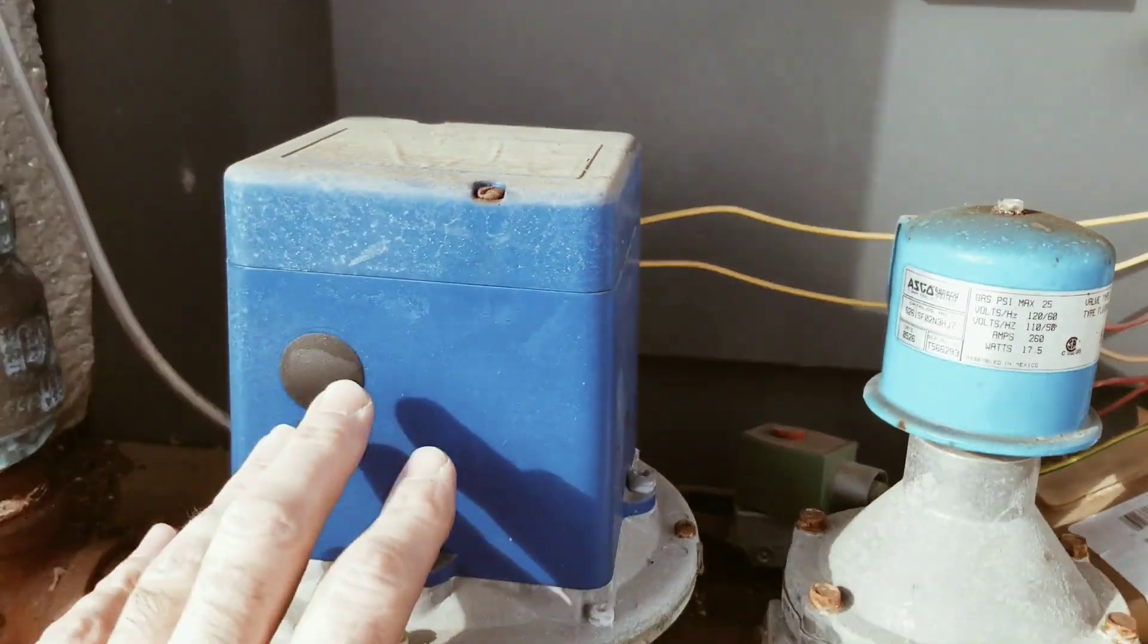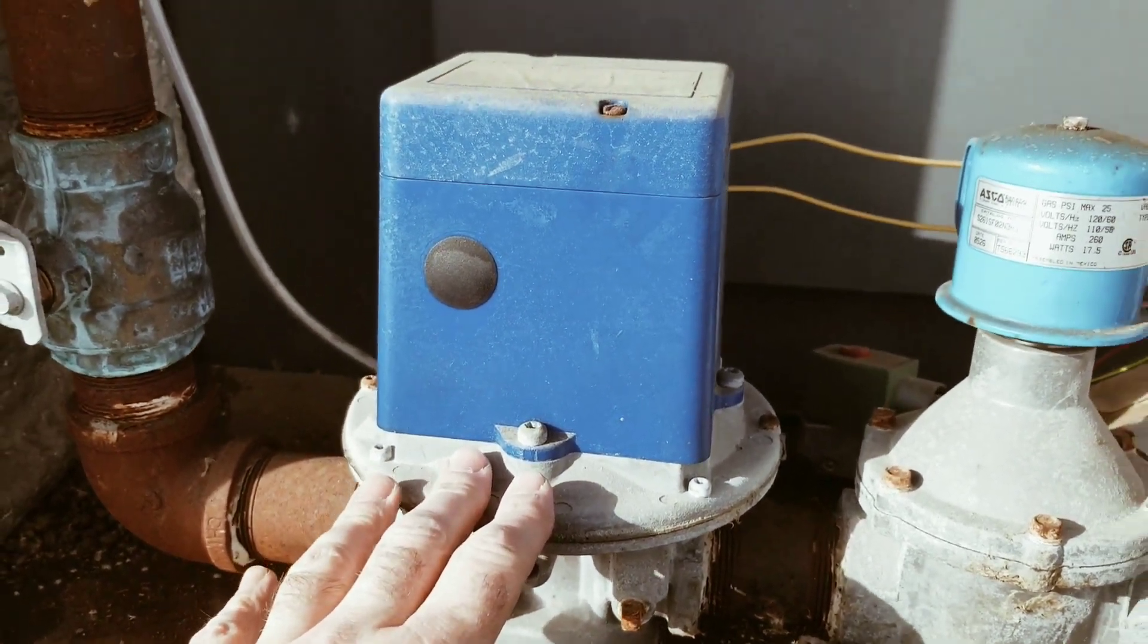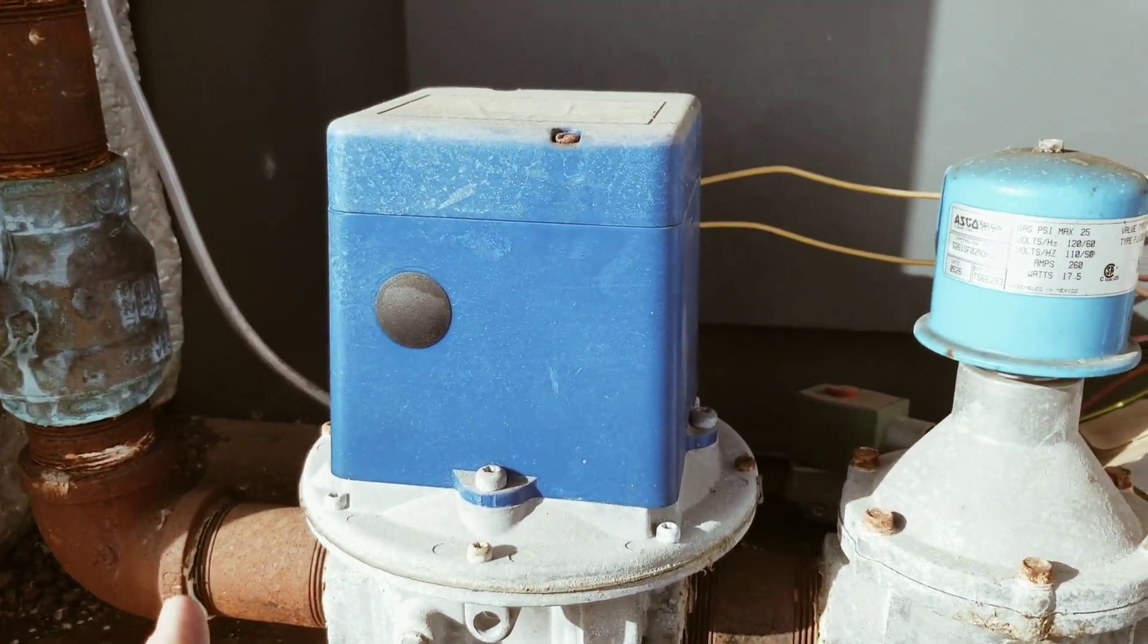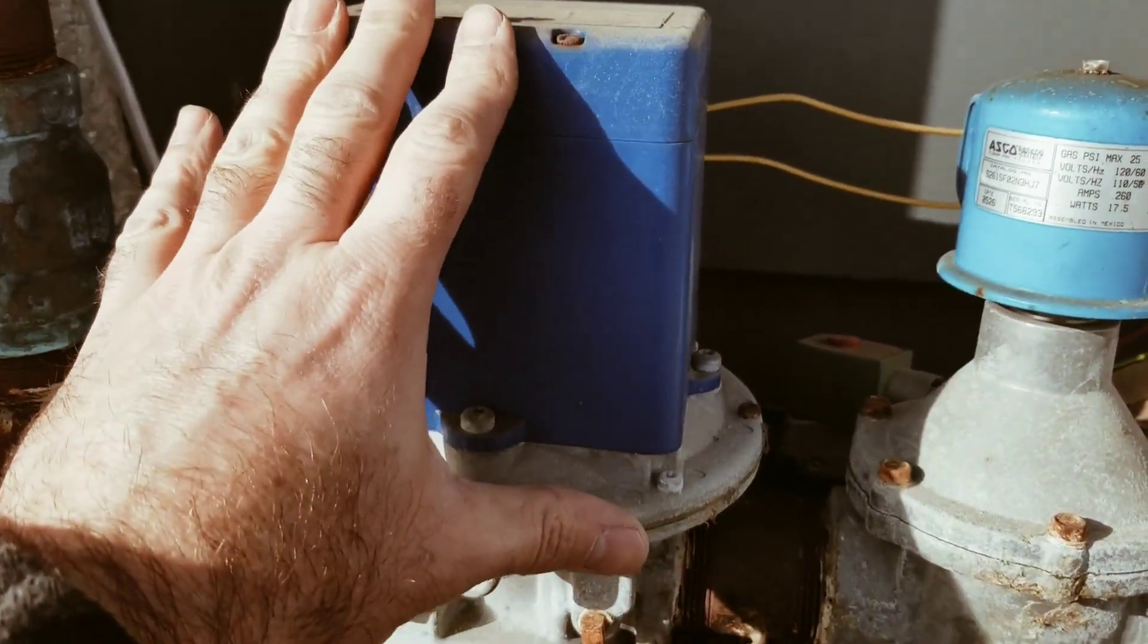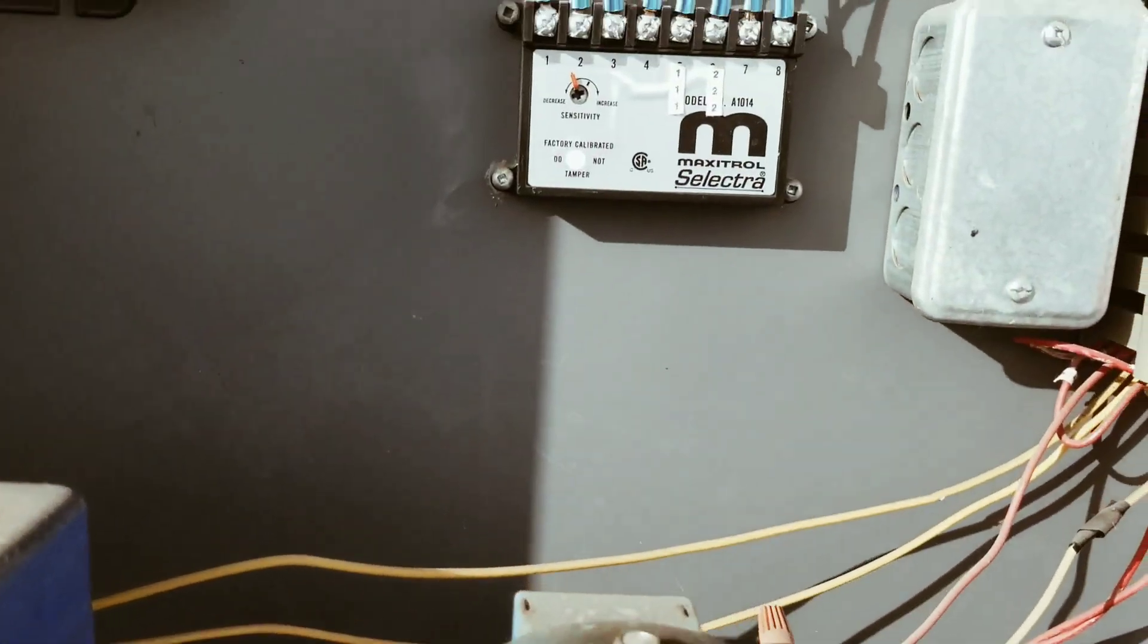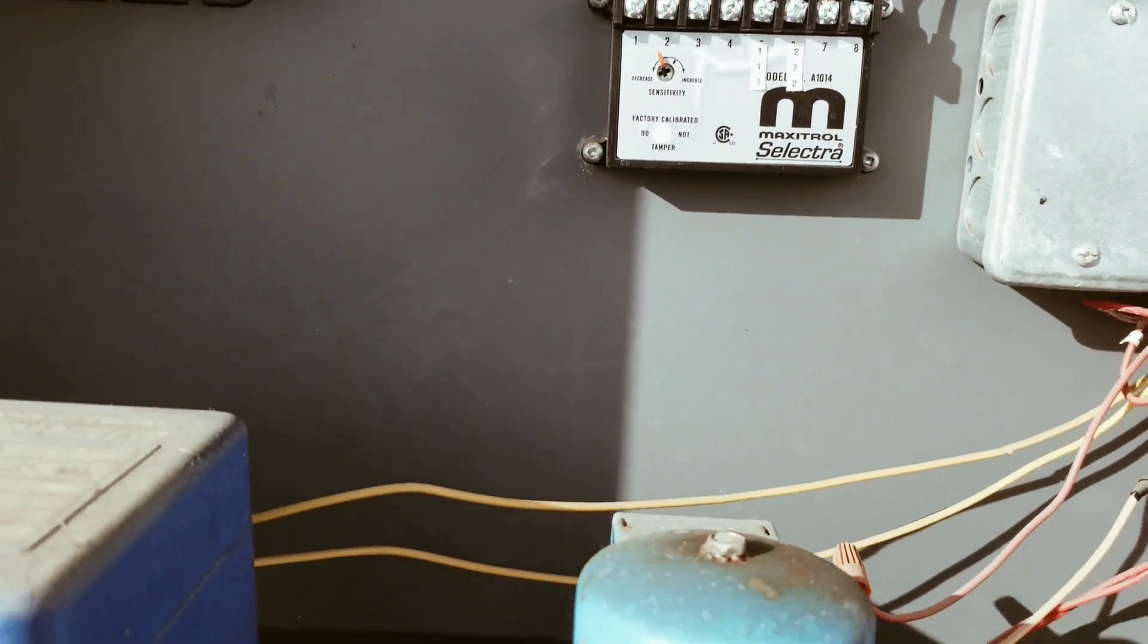Basically this gas valve here will modulate to maintain what you've set it to downstairs. So let's say you want the air to come into the building at 70 degrees. This valve here with this controller and the dial downstairs, that is responsible for doing that.